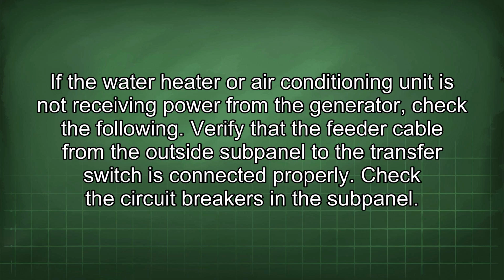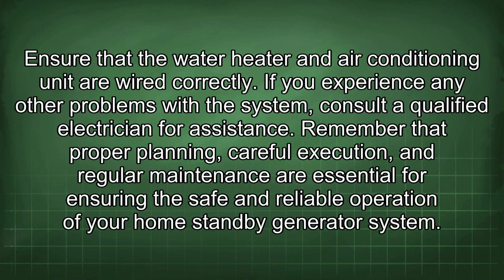If the water heater or air conditioning unit is not receiving power from the generator, check the following. Verify that the feeder cable from the outside subpanel to the transfer switch is connected properly. Check the circuit breakers in the subpanel. Ensure that the water heater and air conditioning unit are wired correctly. If you experience any other problems with the system, consult a qualified electrician for assistance.